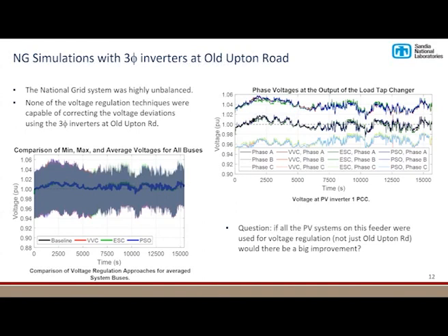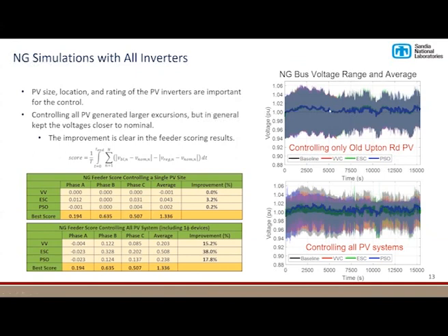But we wondered, well, okay, there's also some single phase devices on this. In the event that we could control all these inverters, how would that improve things? And so we ran that simulation as well. And what we see compared to the top, which is just controlling the large Old Upton Road site, compared to all the inverters, we actually do see quite a bit of improvement because each of the single phase inverters is able to pull that phase toward nominal. And so you get an improvement, in this case, extremum seeking control does quite well, of 15%, 38%, and 17% for the different methods.